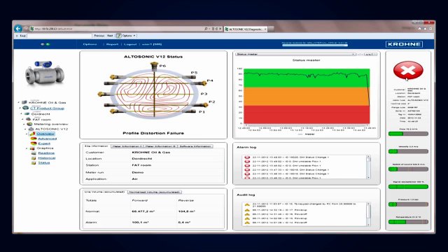The meter goes into alarm. At this moment there is an alarm. There is a serious flow profile distortion. In fact, it's so bad that custody transfer accuracy is affected at this moment in time.